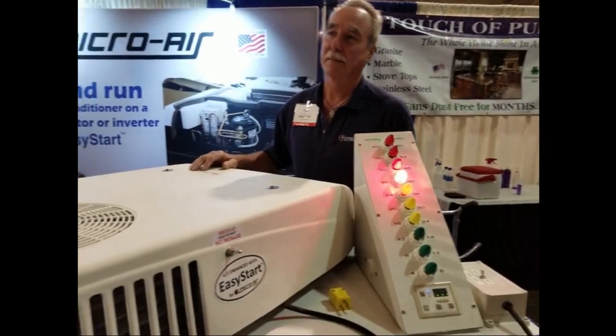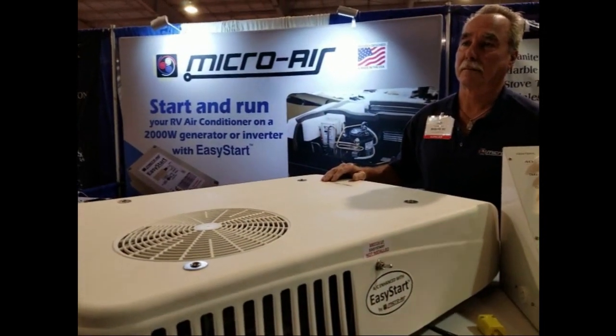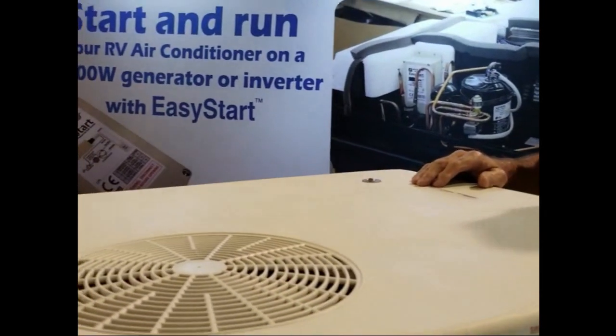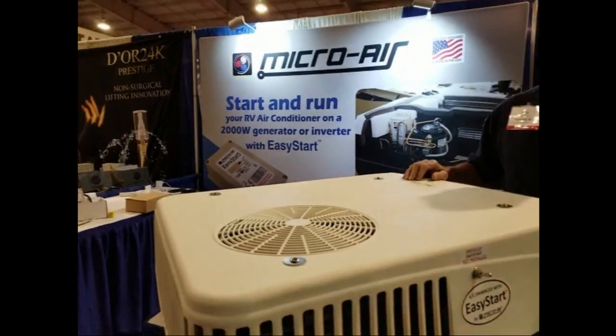So I see by your sign it says that Micro-Air has an EasyStart that can start and run my air conditioner on a 2,000 watt generator or inverter. And I know that on my RV, the air conditioner takes well over 50 amps to start. So how is that possible, Ted?